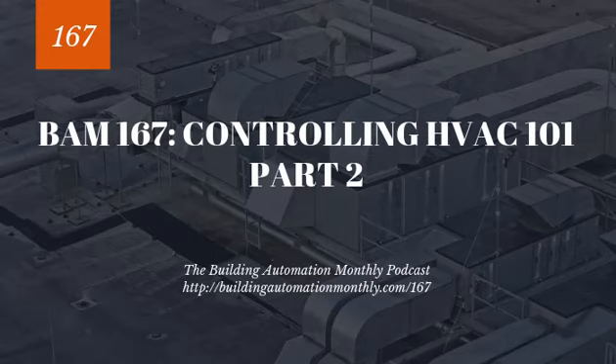Okay, so with rooftop units, we typically have a constant volume flow. We're controlling it, and we really will tend to have maybe some dampers, maybe an outdoor air damper that is typically set at a static position by the balancer. And we typically have a straight return air duct that doesn't have a damper. So then from there, we have our coils, right? And here we tend to have a DX coil and some sort of electric heat or gas reheat.